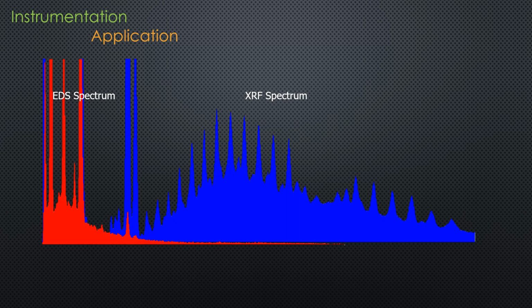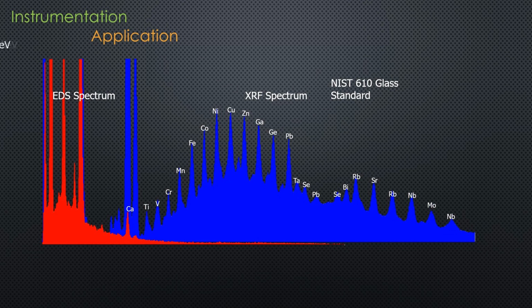This is the NIST 610 glass standard. In the previous spectrum, we showed that electron beam excitation is much better for elements below 2 keV, where in this view, we have Micro XRF showing much better excitation for elements above 2 keV. So this is a fantastic complement.